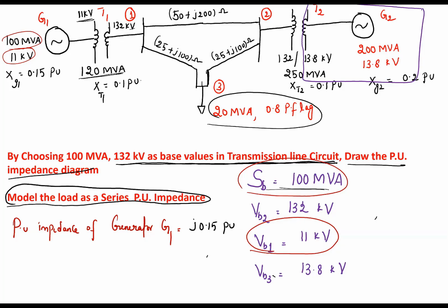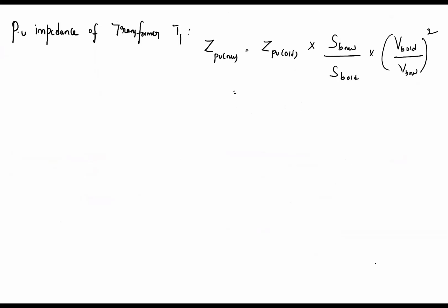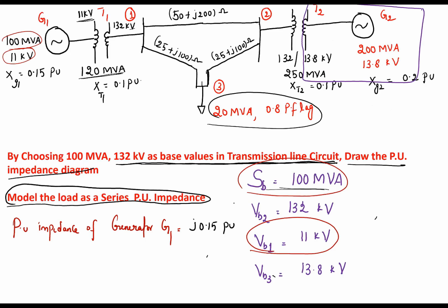So no need to bother about the voltage ratios. You just have to take care of the MVA rating. The new base MVA rating gives this value as J0.1 into new base 100 MVA, divided by the machine base rating of 120 MVA. Either you take the 11 kV side or the 132 kV side, you are going to get this ratio as 1 square, because our base voltage on the 11 kV side is 11 kV only. Machine transformer rating on the 11 kV LT side is 11 kV, so both ratios will be 1. It will become 1 square. So what will be this value? J 0.08 per unit. Okay. So we have calculated the per unit impedance of the second element, the transformer.